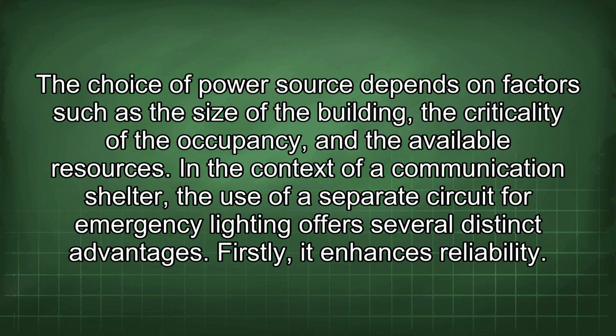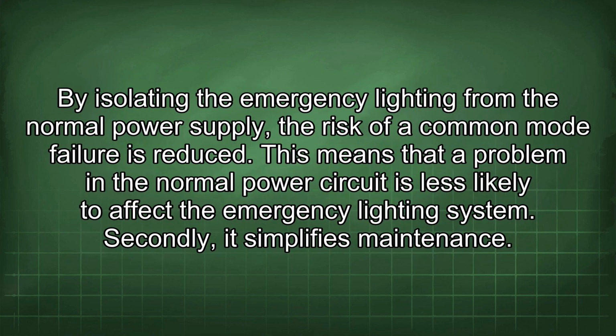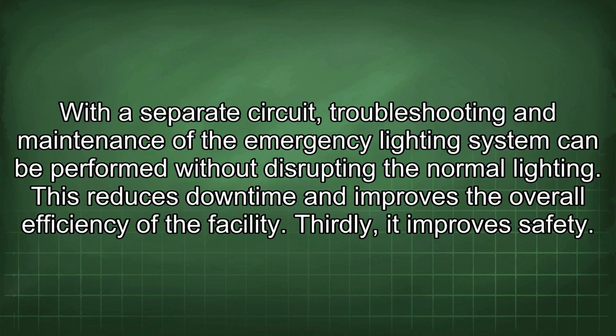Firstly, it enhances reliability. By isolating the emergency lighting from the normal power supply, the risk of a common mode failure is reduced. This means that a problem in the normal power circuit is less likely to affect the emergency lighting system. Secondly, it simplifies maintenance. With a separate circuit, troubleshooting and maintenance of the emergency lighting system can be performed without disrupting the normal lighting. This reduces downtime and improves the overall efficiency of the facility.